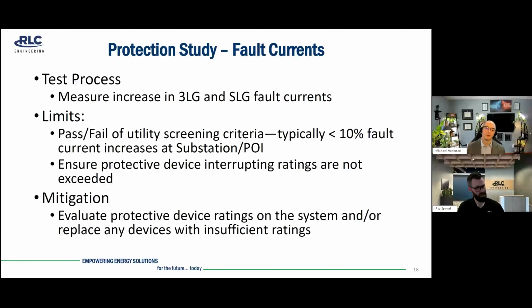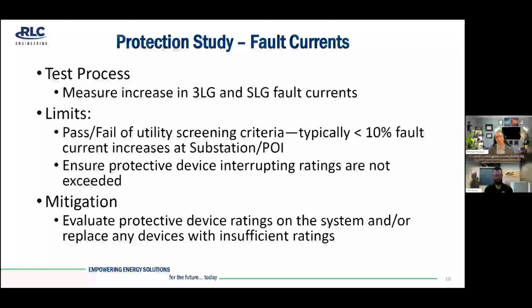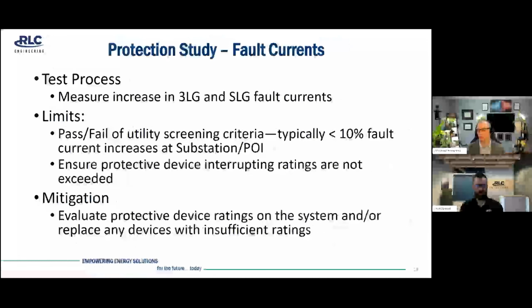evaluations. Some utilities also require just looking at the protective device interrupting ratings and making sure those are not being exceeded. Depending upon what the practice is, you'll either fail the screen and then move towards the more detailed protective device rating, or if you already conducted that, you would replace any devices with insufficient ratings.